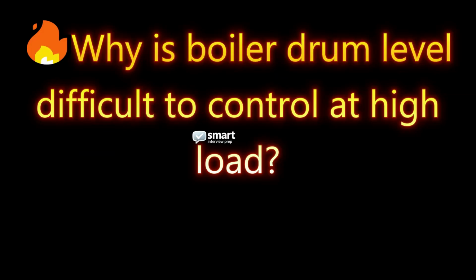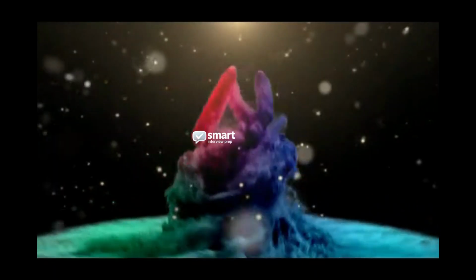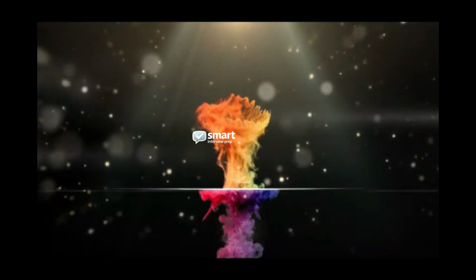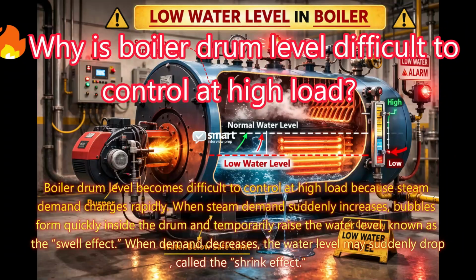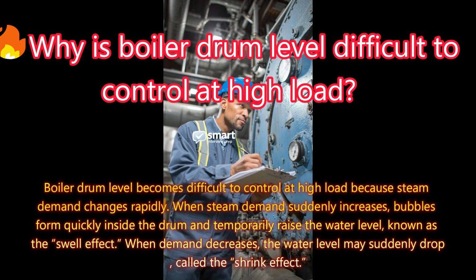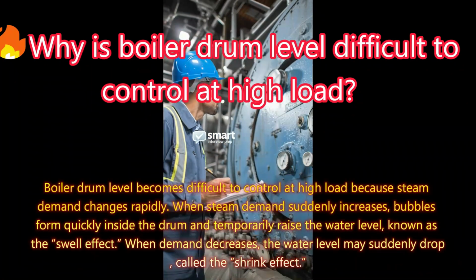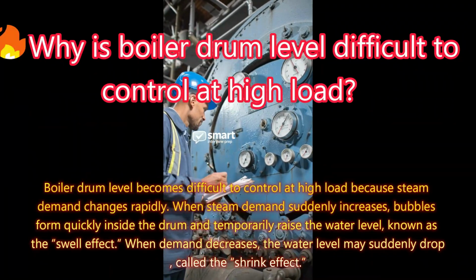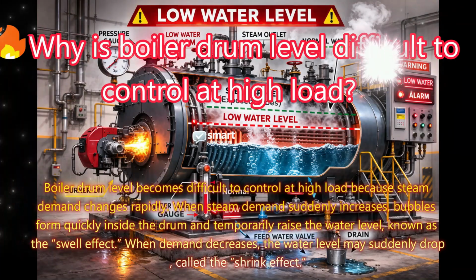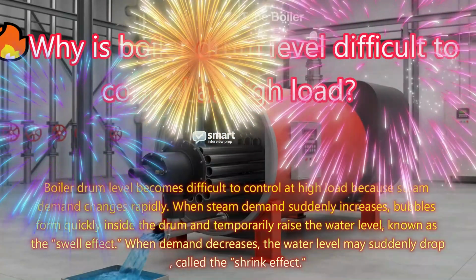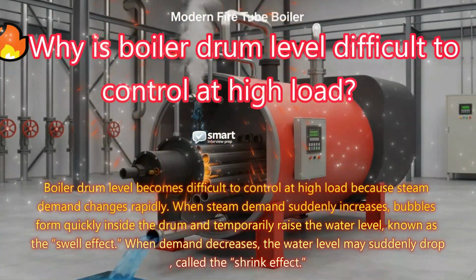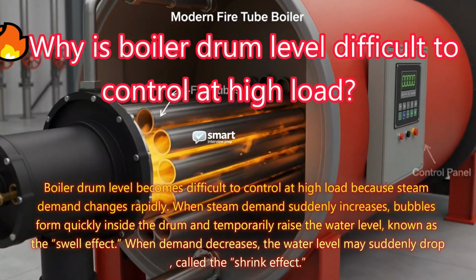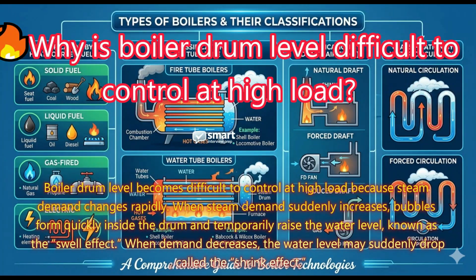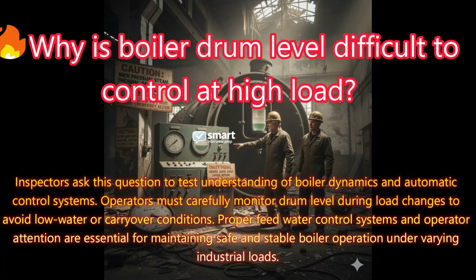Why is boiler drum level difficult to control at high load? Answer: boiler drum level becomes difficult to control at high load because steam demand changes rapidly. When steam demand suddenly increases, bubbles form quickly inside the drum and temporarily raise the water level, known as the swell effect. When demand decreases, the water level may suddenly drop, called the shrink effect.